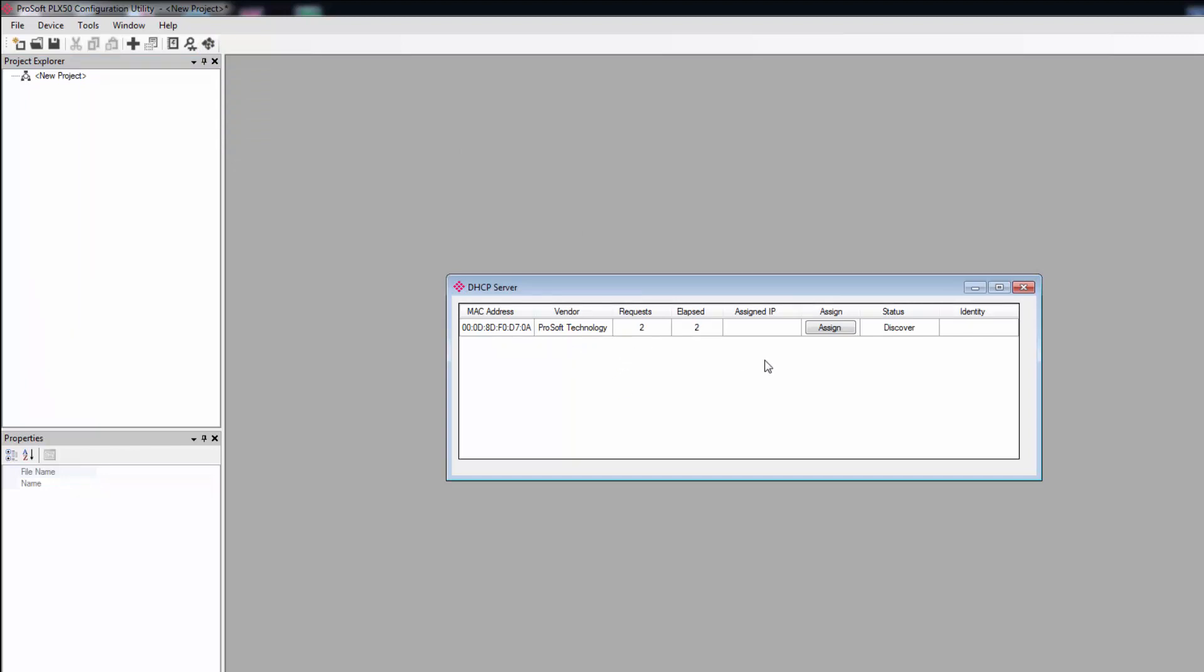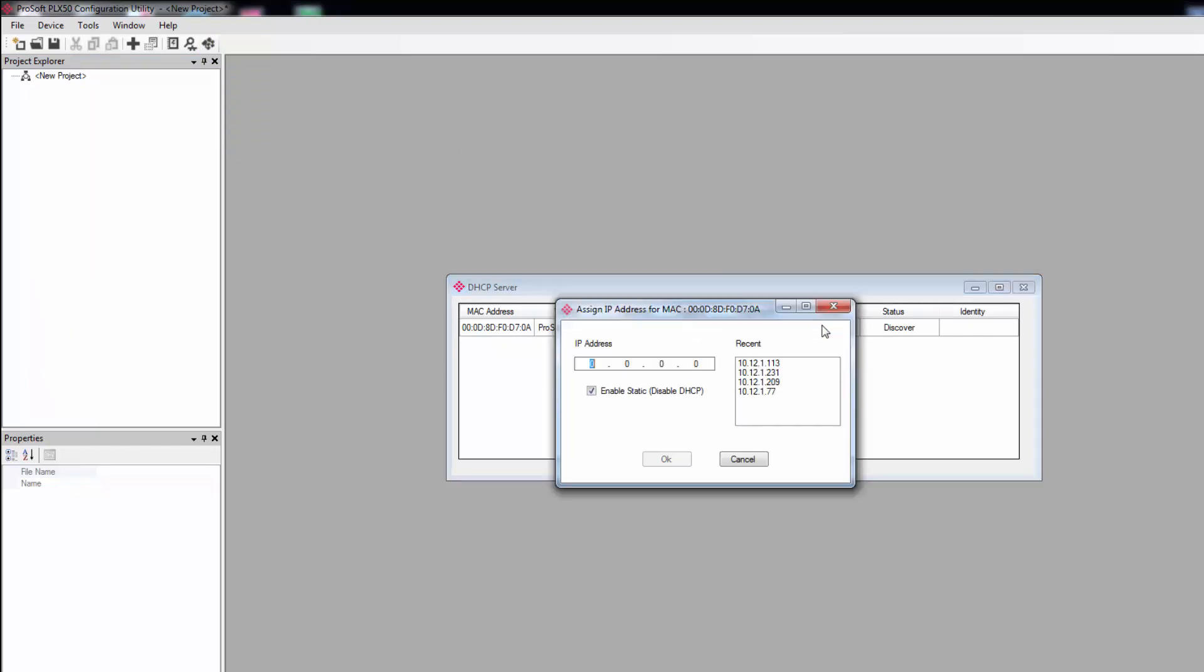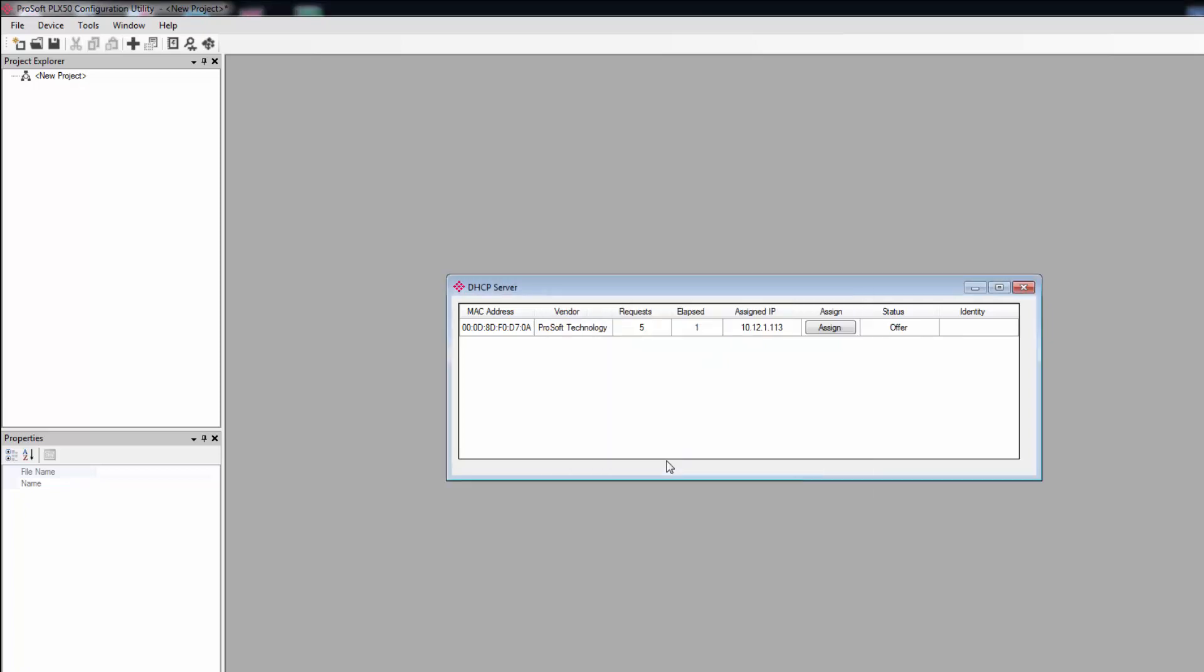Just click the button in the menu bar and here's our gateway. It'll say ProSoft Technology under Vendor. Click Assign and on the window that opens, I'll enter in an IP address that I know is available on the local network. Then select Enable Static and click OK. The bar should turn green, letting you know that the gateway has been assigned the IP address and is now connected.